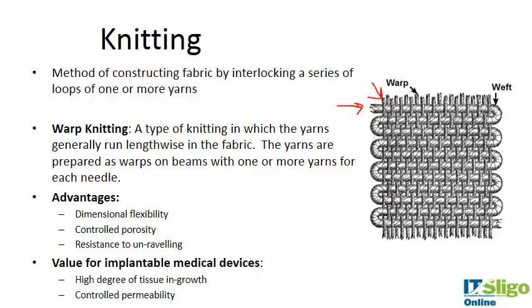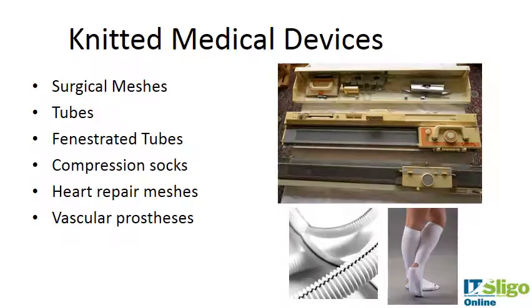You get a nice woven structure. They offer great advantages: they give good dimensional flexibility, they're flexible in every dimension, you can control the porosity, and they are very resistant to unraveling — making them very good for implantable medical devices. You get a high degree of tissue ingrowth, especially in things like hernia mesh repair, and controlled permeability.